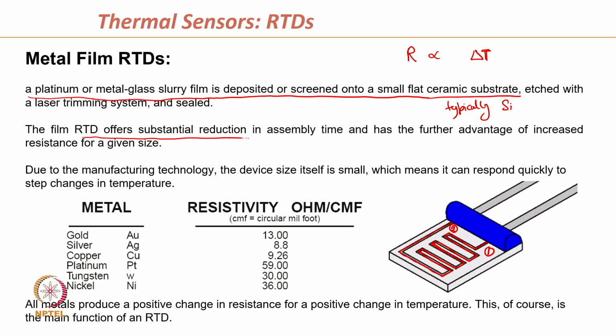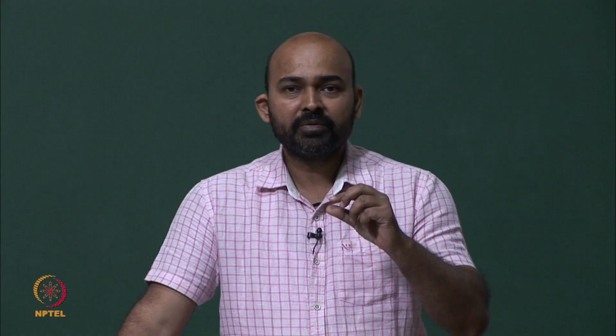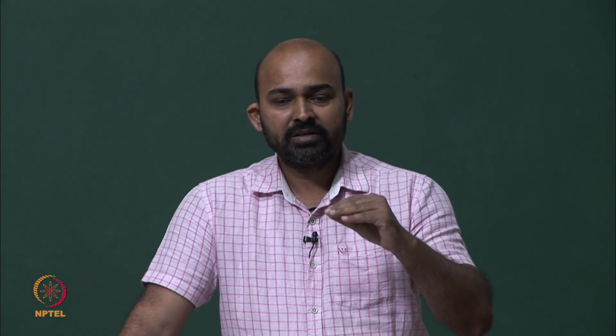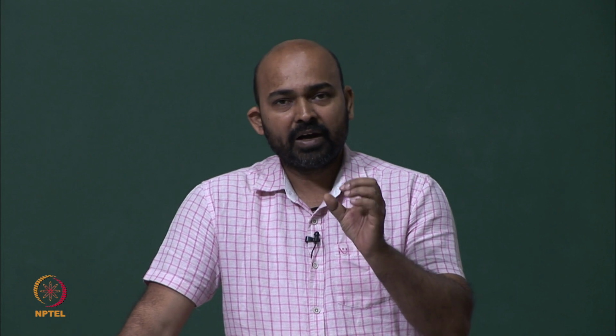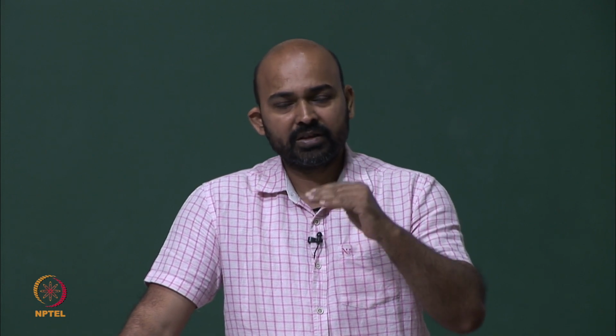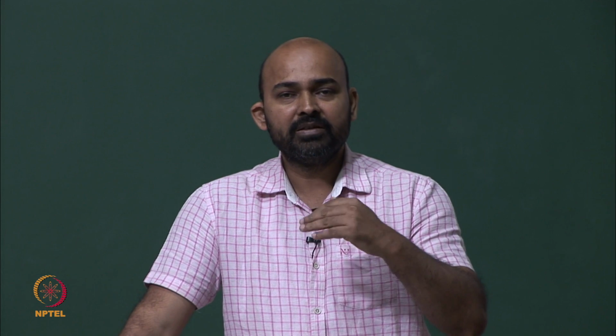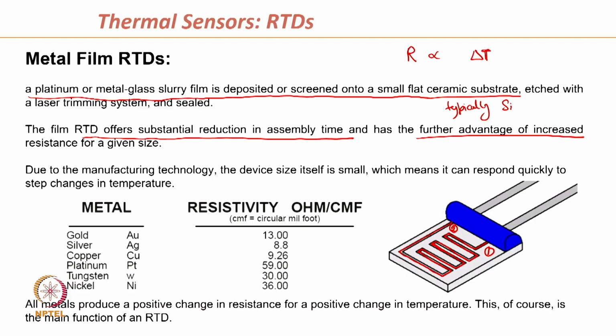So, this film RTD offers substantial reduction in assembly time, because this can be done in a very scalable manner. So, it reduces the assembly time and has further advantage of increased resistance for a given size, because the thickness of film is very small. It means that to have a higher value of resistance, we can further thin down the thin film and we save the material.